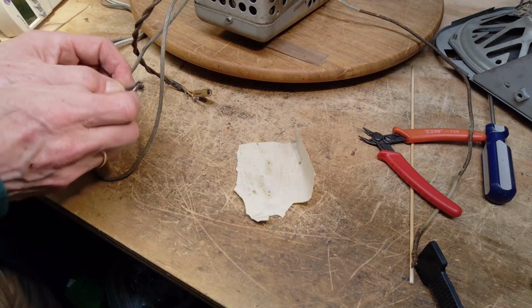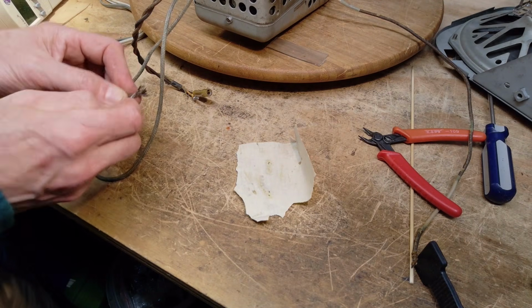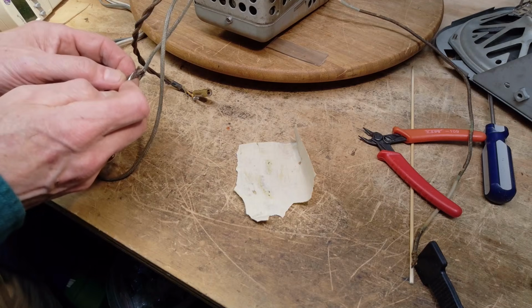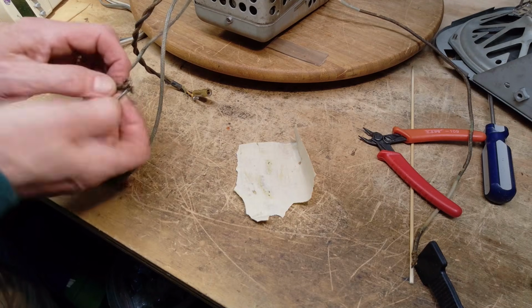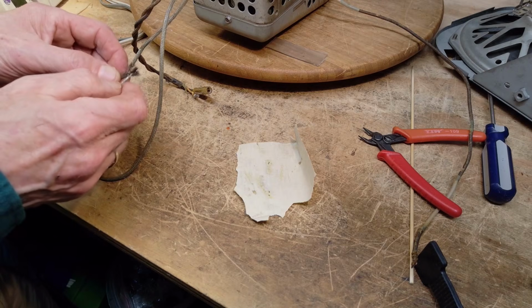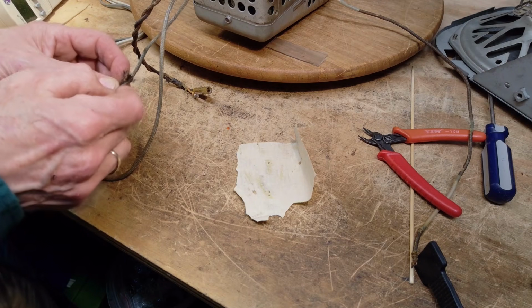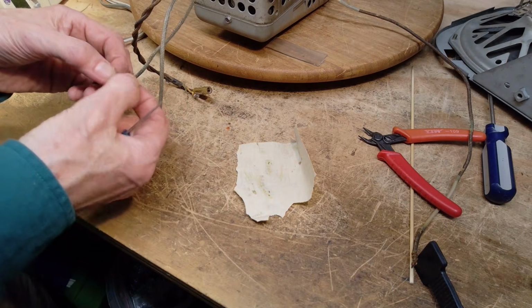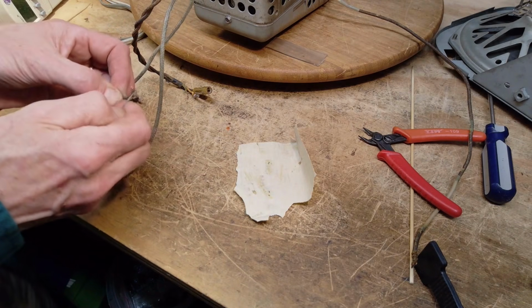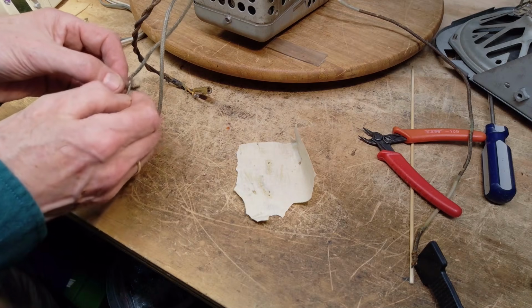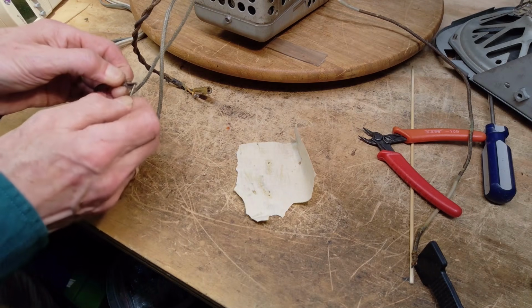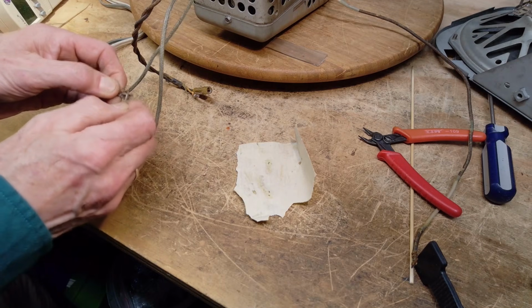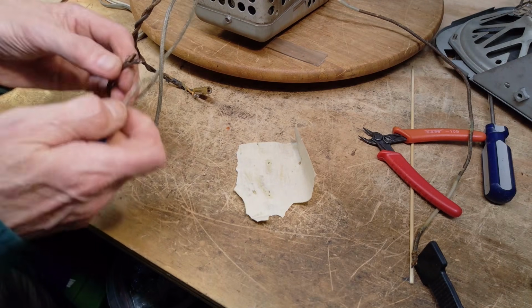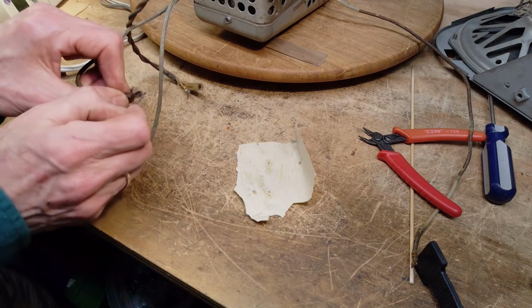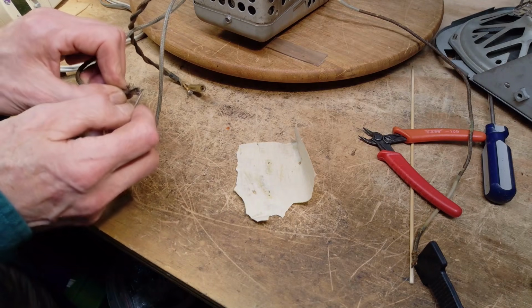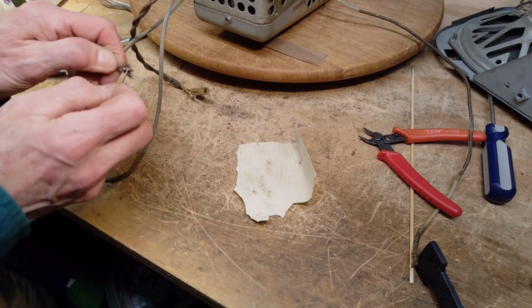I was floored when I first started working at this power company, learning this stuff, because I had no idea. Even though I'd gone to college and studied a bit of electricity, I had no idea. Then I was shocked to find out: inside the lead pipe is the conductor, of course, but what's the insulation? Paper. I couldn't believe it. Paper insulation in high voltage cables under the streets. High voltage being 8,000 volts - 8,000 volts phase to ground. I can't remember now, 13.8 and 8,000.